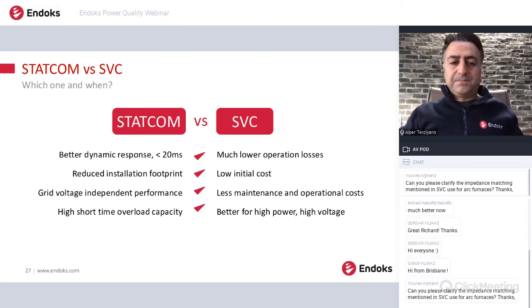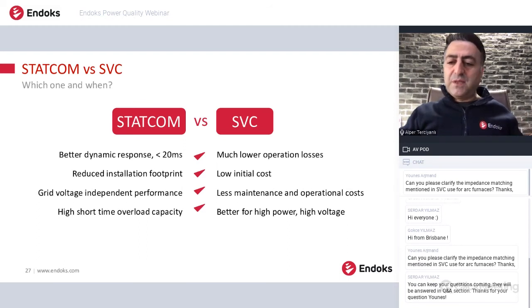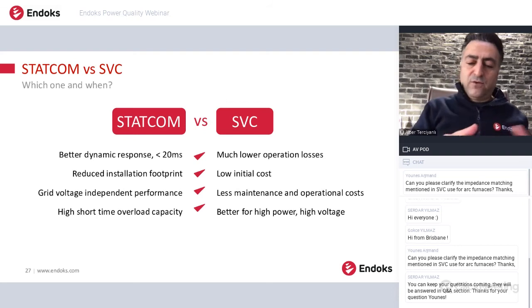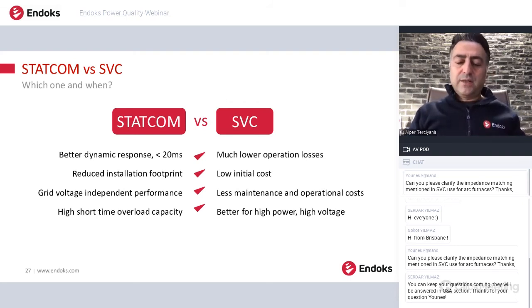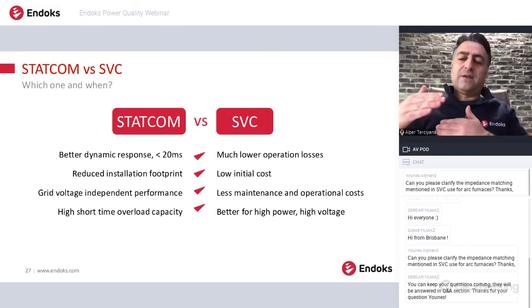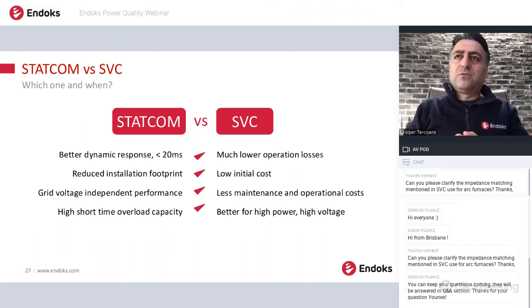STATCOM: better dynamic response, reduced installation footprint, grid voltage independent performance, and high short time overload capacity. Since the converter is controlled by us as a voltage source, we can inject the current required in a controlled way. And for example, in a STATCOM, you can inject more current for short time periods, because it is up to the cooling system, or up to the temperature rise on the devices. So for shorter periods, you can inject more power. For example, I will explain in the next slides.